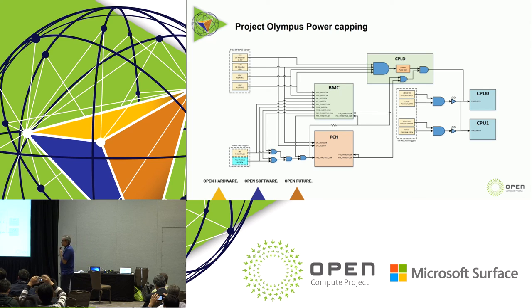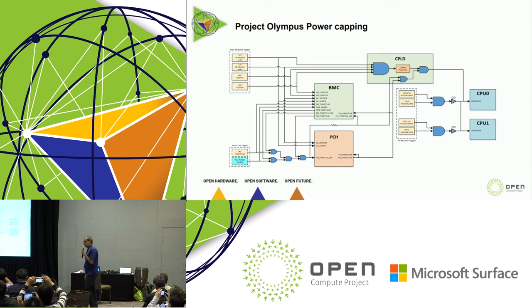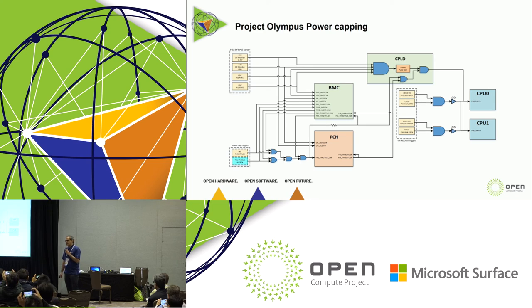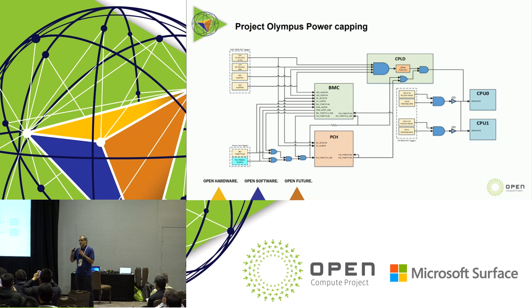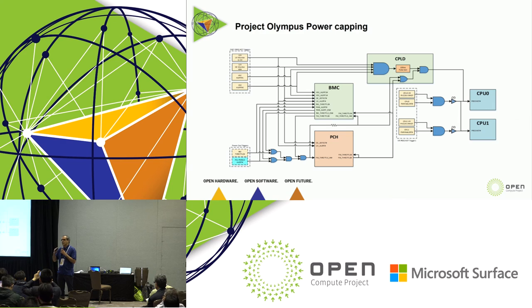This block diagram shows how we realize power capping at the server and rack level in Project Olympus. As Dave mentioned, we have two mechanisms. The first is called CPU throttling or proc hot — that's a signal connected to the Intel chipset. If that signal is asserted, after very low latency — maybe a few milliseconds — the frequency drops to a minimum level, called low frequency mode, reaching the lowest possible power consumption mode. That's a fast reaction to a power event when required.